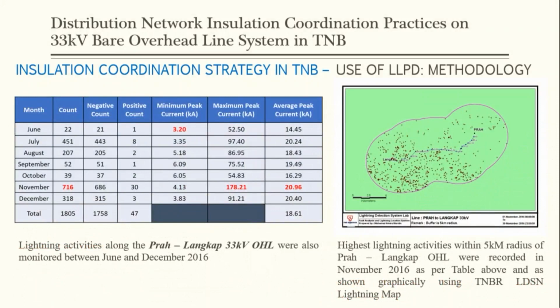And then the second part was to monitor the lightning activities along the Prah Langkap overhead line between June to December 2016. The highest lightning activities within a 5 km radius of the Prah Langkap overhead line were recorded in November 2016, as per the table shown and as shown graphically using the TNB LDSN lightning map. So all the dots represent lightning strikes near the line. And we can see that in November 2016, it recorded the highest number of lightning activities near the line. You can see the line here. Okay, so this is the line. So we have a lot of lightning activities within the 5 km radius of the line.